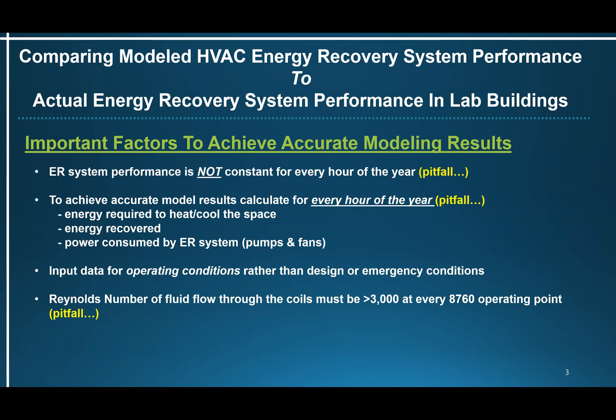Important factors to achieve accurate modeling results. Energy recovery system performance is not constant for every hour of the year. Most commercial models calculate the system performance using a constant efficiency value for all 8760 hours of the year. But in actuality, the system efficiency changes as outside air temperature and humidity change and as building operating conditions change, such as air volumes, supply air temperatures, exhaust air temperatures, etc. So energy recovery system performance needs to be calculated and input for every hour of the year.